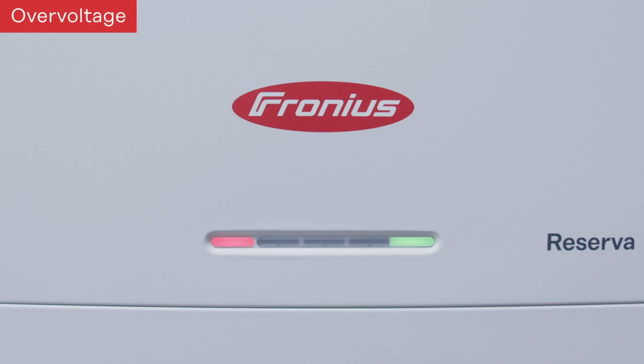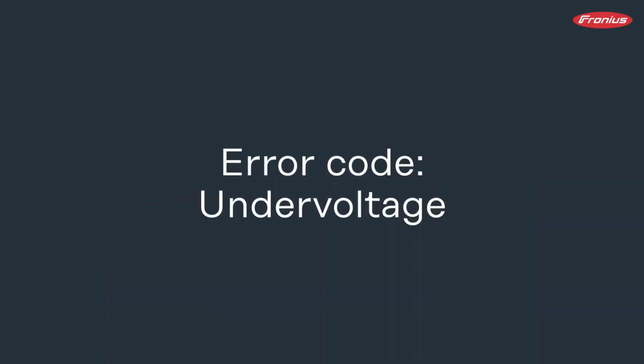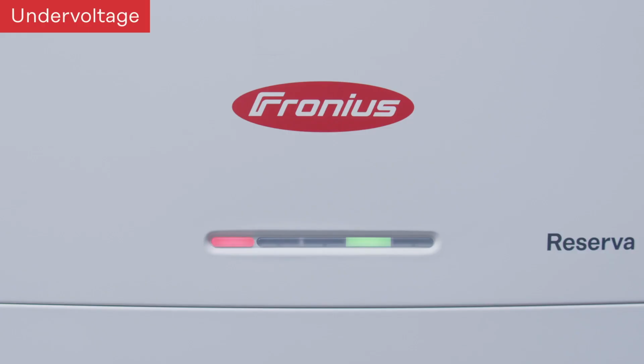overvoltage. And in this case, there can be an overvoltage coming from the inverter or from another failure source to the battery, and then you will get this LED status for overvoltage. Second LED status is an undervoltage, and in this case it can be that the battery is being discharged, and at a specific level it will show you an undervoltage failure code, and this is the LED status that you can see here.